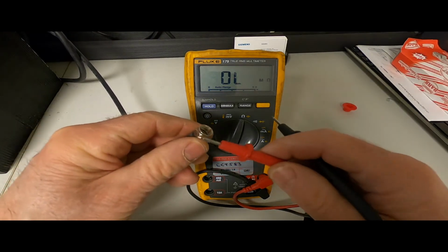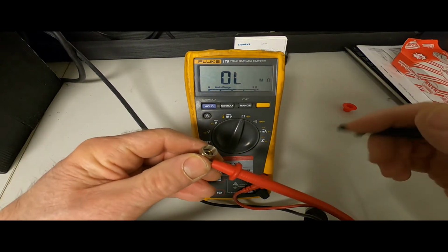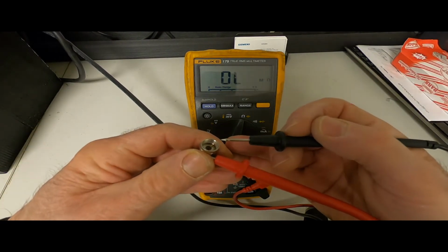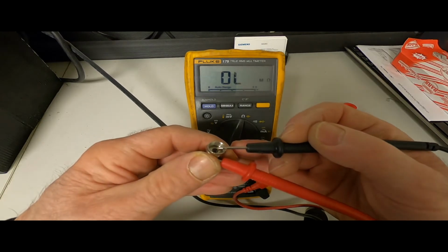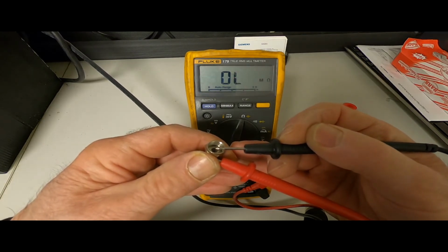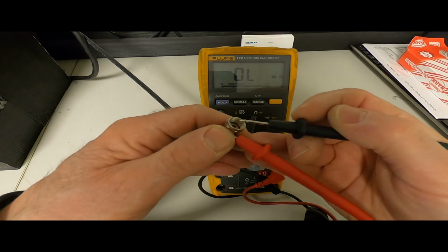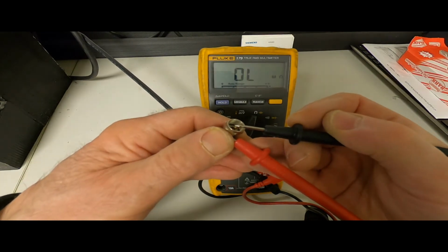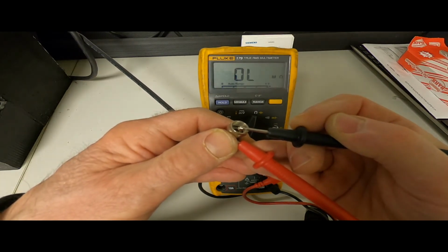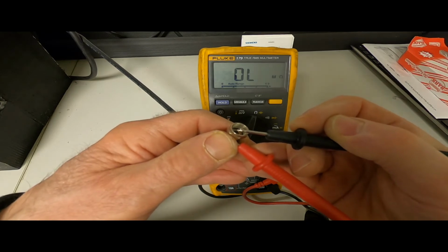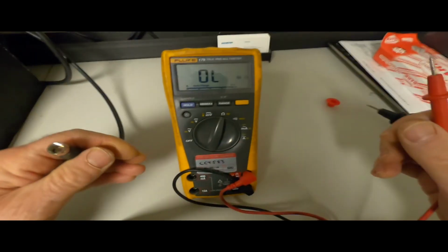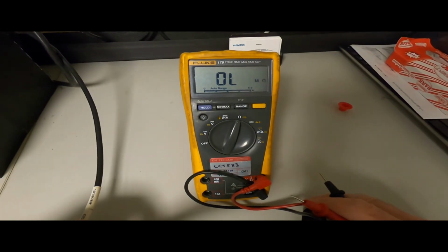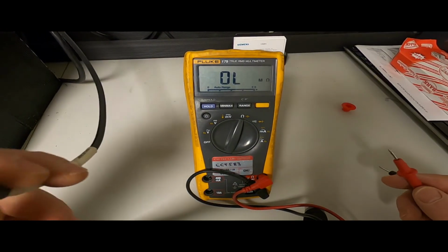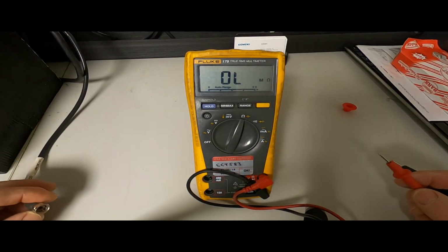Here's a situation where we have a bad connection. So when we take the ohm meter and place it across the F connector, we still read an open. So that would mean that the cable may have a break, or it's not connected properly at the flow sensor end, or perhaps there was water infiltration and there was corrosion that took place, but that allows us to identify the fact that we have an open circuit.